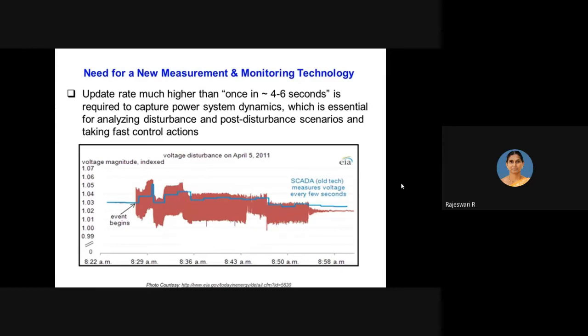The actual measurement of voltage fluctuation or variation around the nominal value in per unit is shown by the new measurement technology, shown in red. You can compare these two plots - SCADA is only focusing on the steady state value. It's not focusing on the dynamic value.